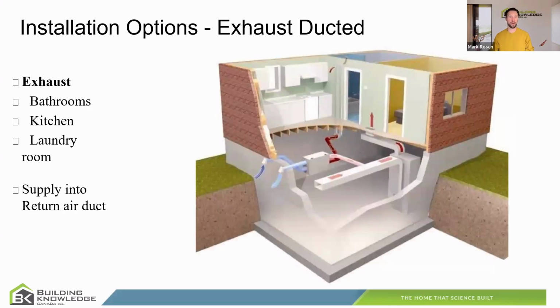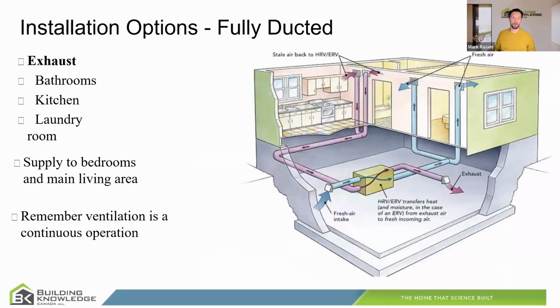The next level up from that would be to look at what's called a dedicated exhaust strategy or a dedicated return strategy, where you extend the exhaust side all the way to the contaminant point sources, where we were already serving them with bath fans, kitchen exhausts, etc. And you pull air directly from those spaces, but you supply it through the central ductwork again. And the third strategy is what's called a fully ducted solution, where you have dedicated ductwork for the ventilation system that both supplies and exhausts air. And this may be something that exists alongside central ductwork or in homes that don't have central ductwork.